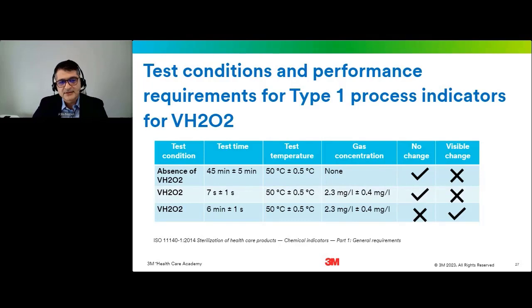Now, let's have a look at the test conditions for a type 1 in vaporized hydrogen peroxide processes. Following the exposure to a specified test condition, the process indicators shall perform as shown in this table in order to be designated as a type 1 indicator for hydrogen peroxide. In the absence of hydrogen peroxide, there should be no change, meaning no change markedly different from the visible change as specified by the manufacturer. So the manufacturer of that chemical indicator defines what is a visible change and what is not, based on the method: color or color change, moving front, or other form.